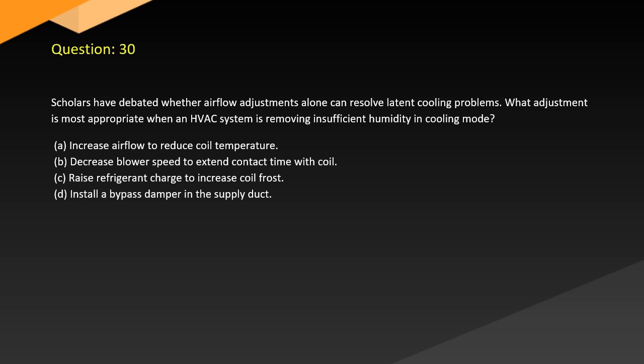Question 30. Scholars have debated whether airflow adjustments alone can resolve latent cooling problems. What adjustment is most appropriate when an HVAC system is removing insufficient humidity in cooling mode? A. Increase airflow to reduce coil temperature. B. Decrease blower speed to extend contact time with coil. C. Raise refrigerant charge to increase coil frost. D. Install a bypass damper in the supply duct.